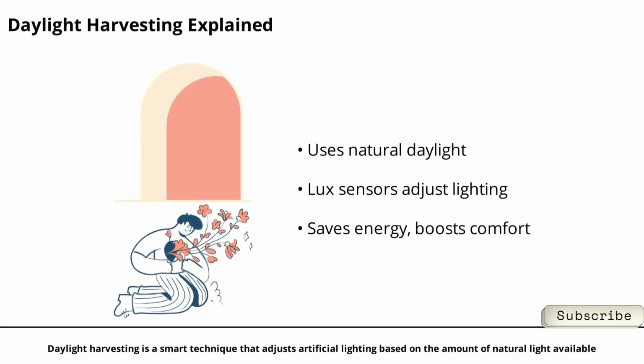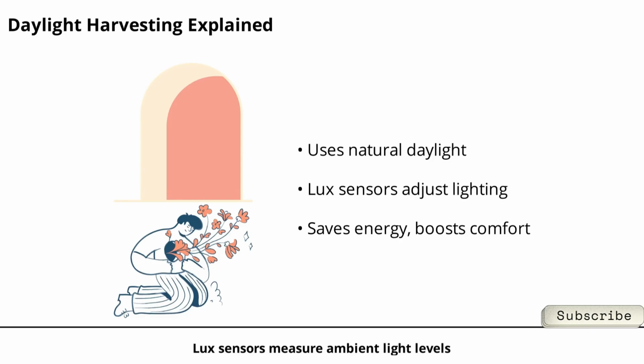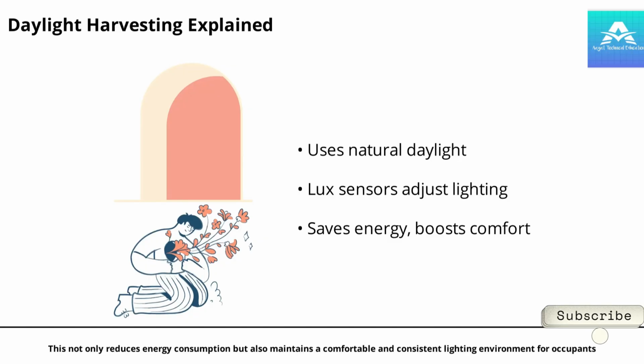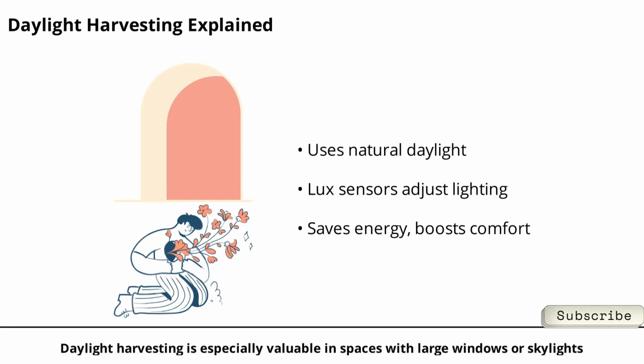Daylight harvesting is a smart technique that adjusts artificial lighting based on the amount of natural light available. Lux sensors measure ambient light levels, and when sunlight is sufficient, the system dims or turns off artificial lights to save energy. For example, if ambient light exceeds 500 lux, lights may be dimmed to 40%. This not only reduces energy consumption, but also maintains a comfortable and consistent lighting environment for occupants. Daylight harvesting is especially valuable in spaces with large windows or skylights.